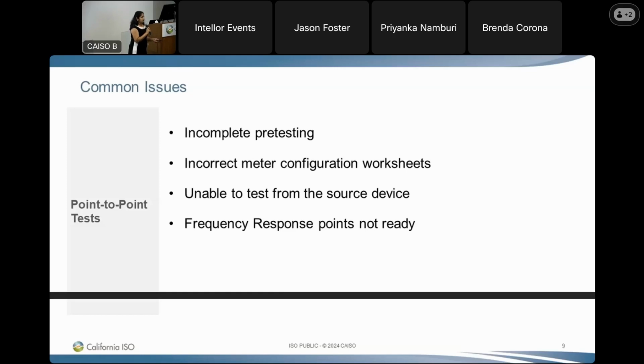For the point-to-point test, as mentioned before, we need pre-testing and a communication check done. If the pre-testing isn't done completely or thoroughly, it will cause issues during the point-to-point test. As many of you know, it's really hard to get an appointment on the EDAS fieldwork calendar, so we highly recommend making good use of the time allocated. Thorough pre-testing will definitely help during the point-to-point testing.